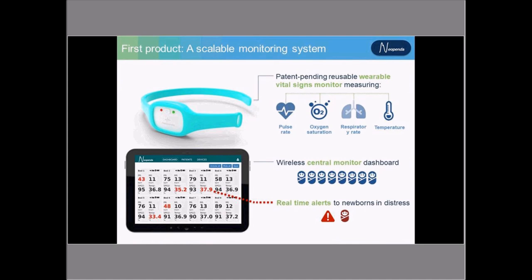That's exactly what we're doing. We've created a patent-pending wearable vital signs monitor that continuously measures four different vital signs: pulse rate, respiratory rate, blood oxygen saturation, and temperature — all in a simple headband or armband. The vital signs from all of these devices wirelessly connect to a centralized dashboard on a single tablet. A nurse can efficiently view the health status of all the babies in the room just by looking at one screen. And if any baby's vital signs go outside of the healthy range, a nurse is immediately alerted so she knows where to direct her attention most efficiently.